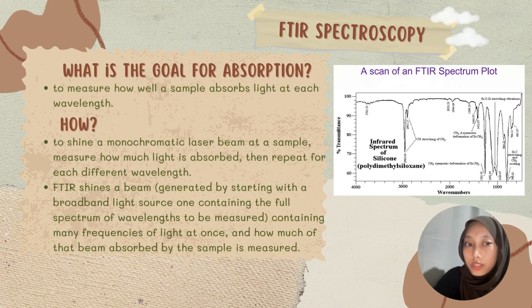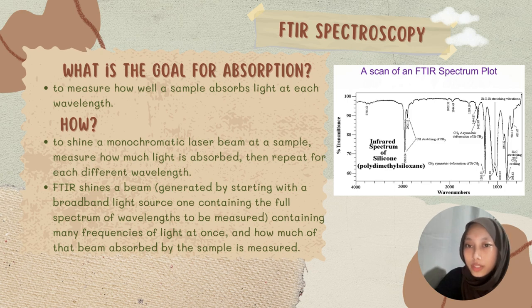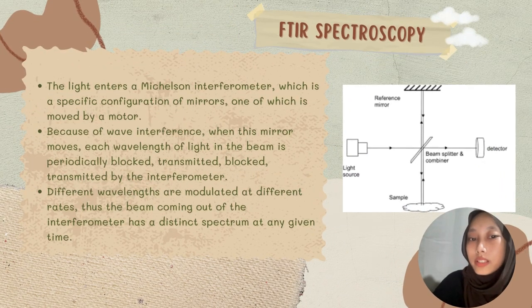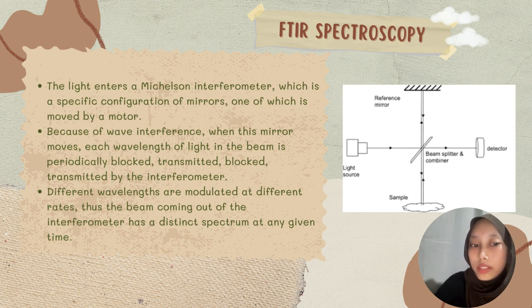The goal of absorption is to measure how well a sample absorbs light at each wavelength. FTIR shines a beam generated from a broadband light source — one containing the full spectrum of wavelengths — containing many frequencies of light at once, and measures how much of that beam is absorbed by the sample. The light enters a Michelson interferometer, a specific configuration of mirrors, one of which is moved by a motor. Because of wave interference when this mirror moves, each wavelength of light in the beam is periodically blocked and transmitted by the interferometer.